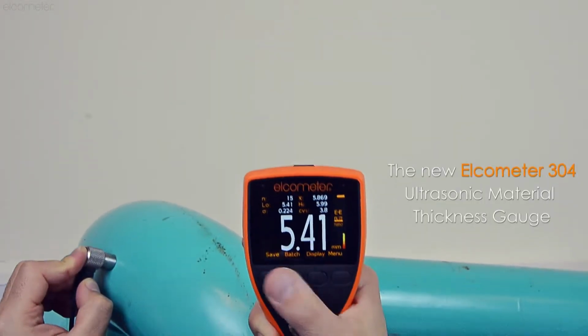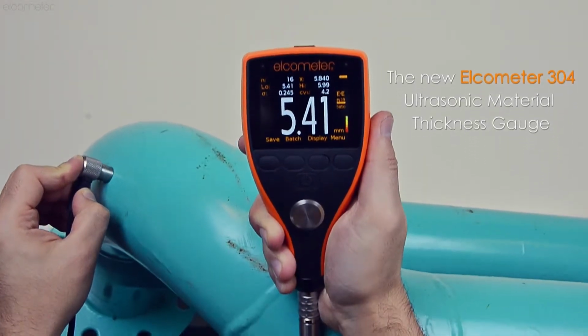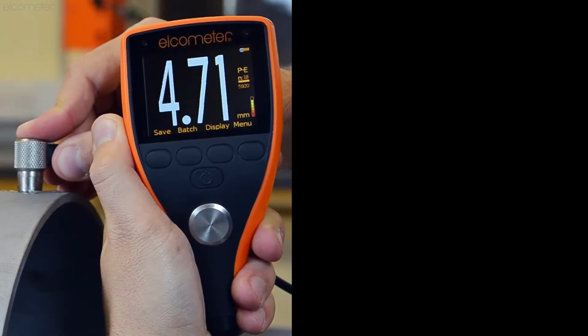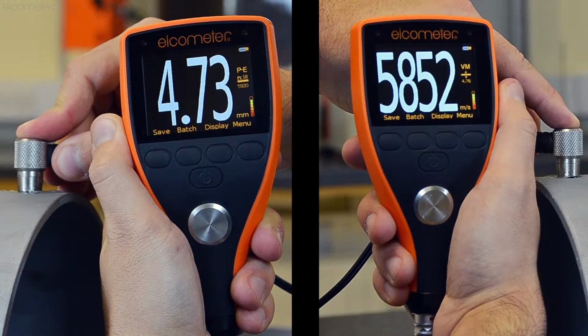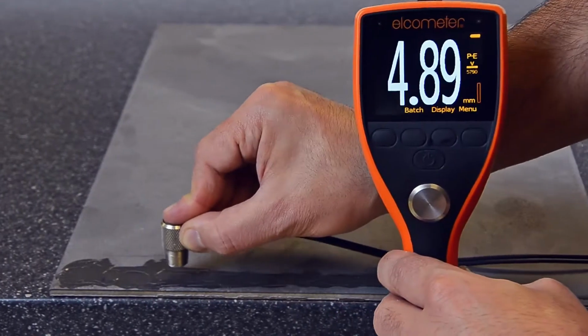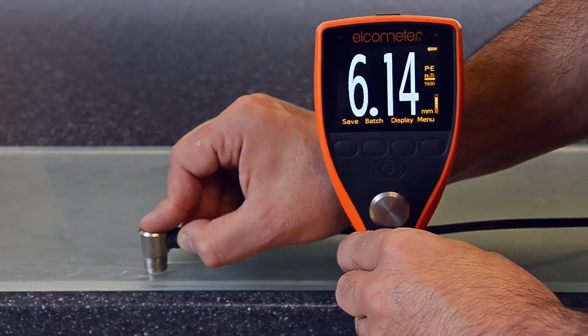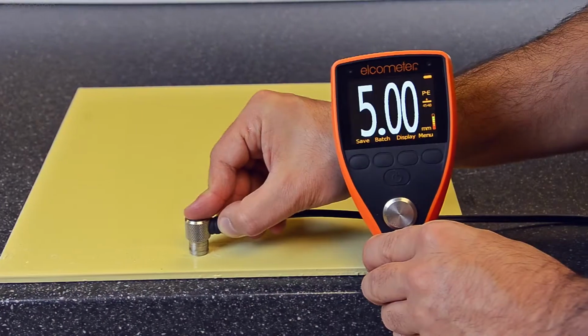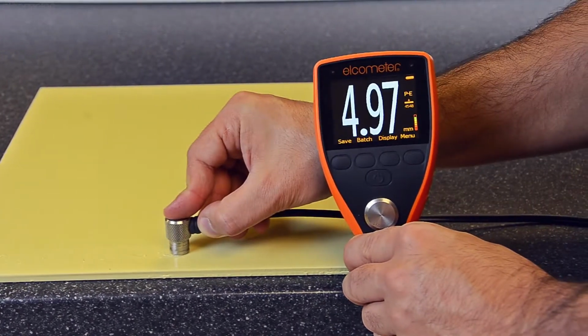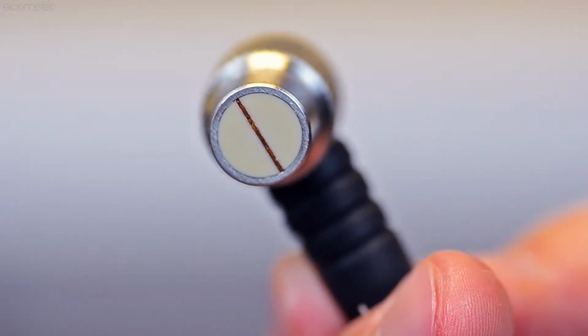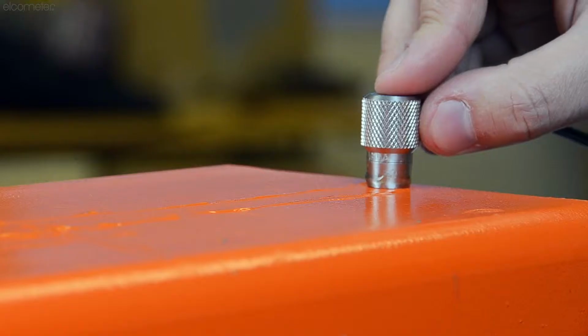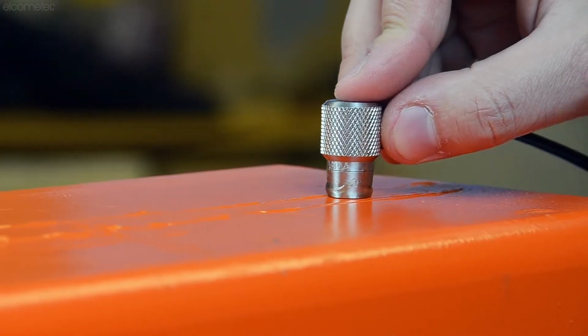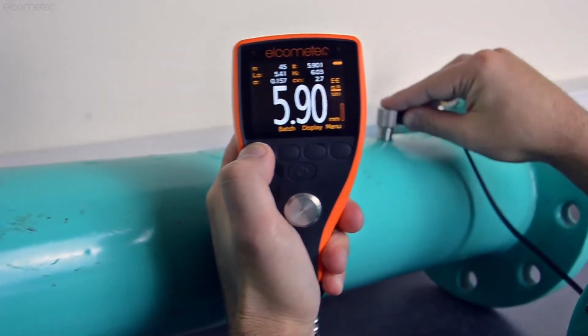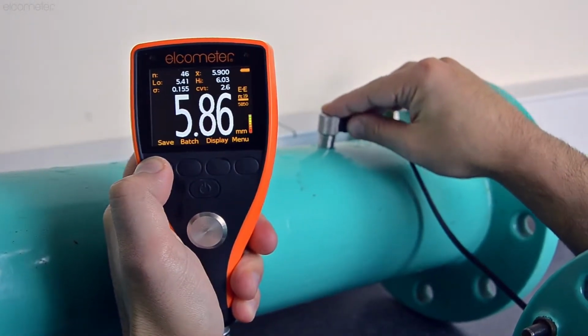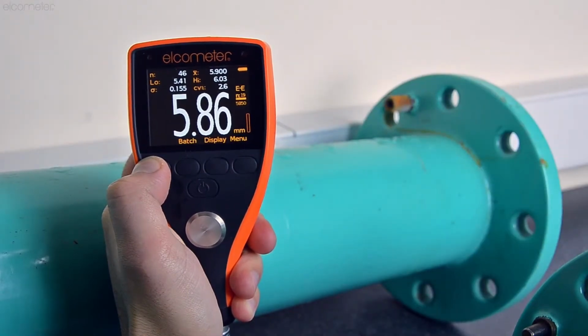The Elcometer 304 is an ultrasonic material thickness gauge designed to measure the thickness, or sound velocity, of most materials, such as metals, plastics, glass, epoxies, and ceramics. Using a dual element transducer, the Elcometer 304 has the ability to measure the substrate thickness, even when it is coated with up to 2 mm of paint. Ideal for when you need to measure the thickness of a coated material without damaging the coating.